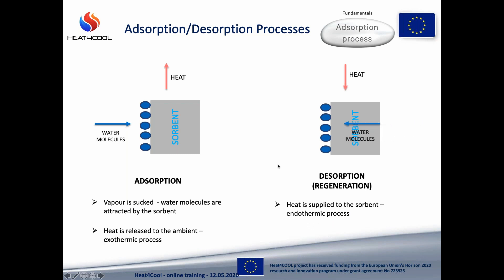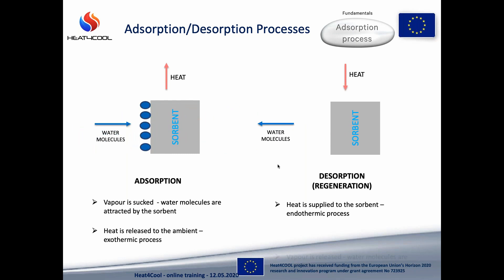The water molecules are expelled from the sorbent — the water vapour is released. When we have the regenerated sorbent we can cool it down and then the adsorption process can start again. And what happens with water? If we want to evaporate it in the next step we have to condense it, for example in the right bulb again. In Fahrenheit machines we use zeolite and silica gel as sorbent, and pure water as refrigerant.